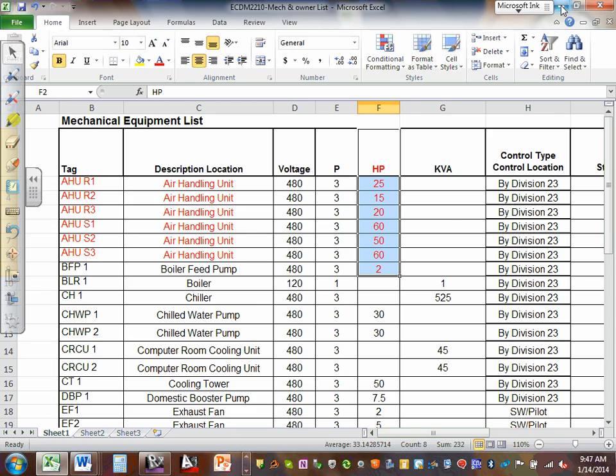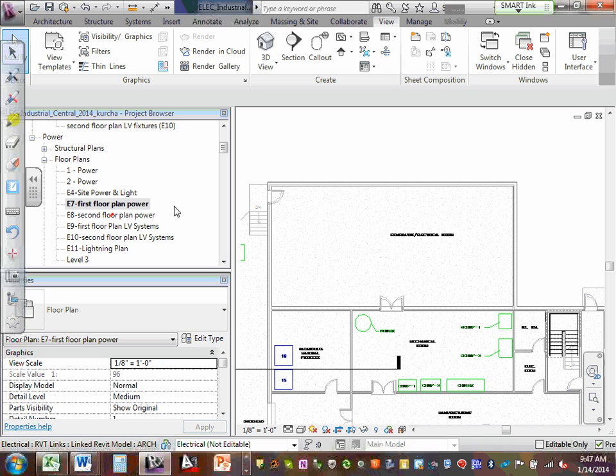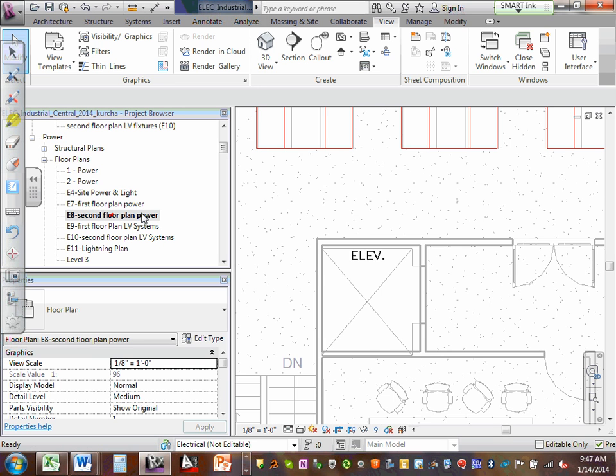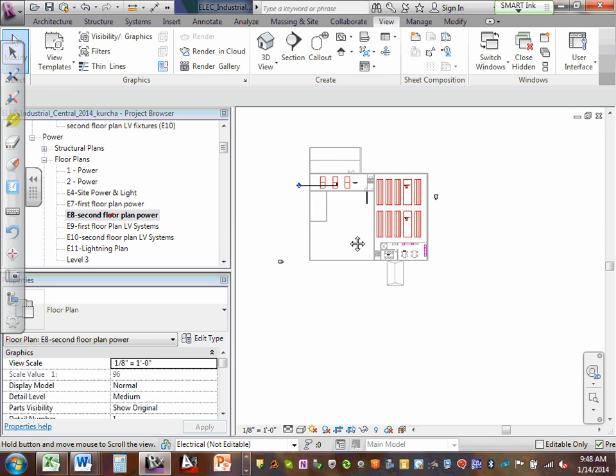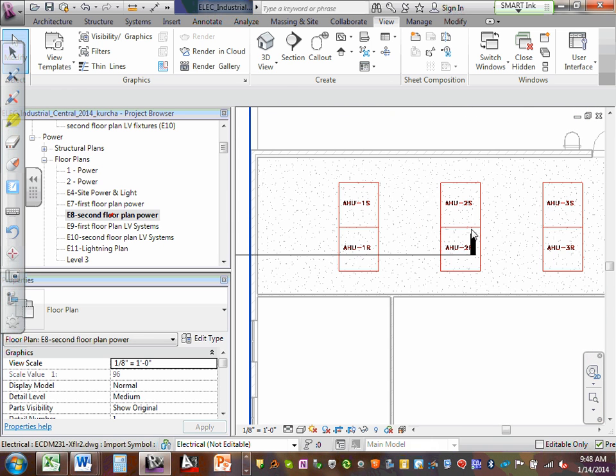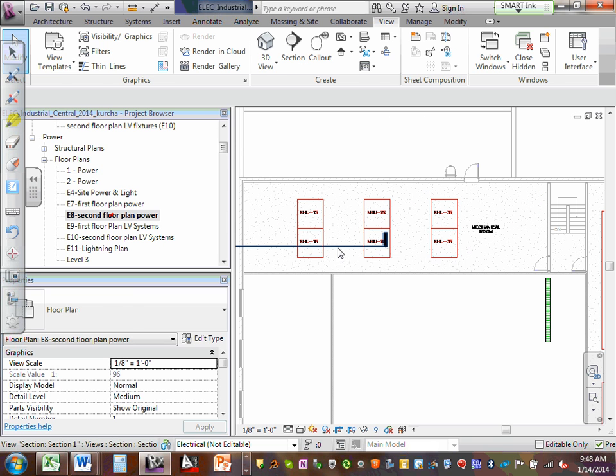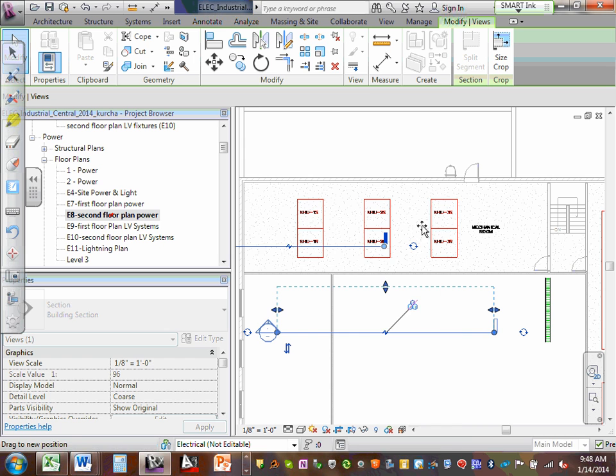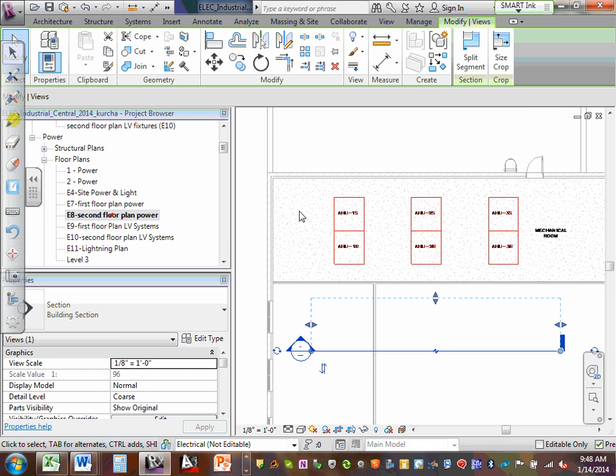Generally, air handling units, and even more so rooftop units, which is an air handling unit that sits on the roof, are sized by either CFM capacity, which is cubic feet per minute, the air movement that they can push, their maximum air output, or by tonnage. Okay, a 4-ton air handling unit is 2,000 CFM. Excuse me, a 5-ton air handling unit is 2,000 CFM. Okay, 400 CFM per ton. Maybe you want to make a note of that because that'll be useful information for you in the future.